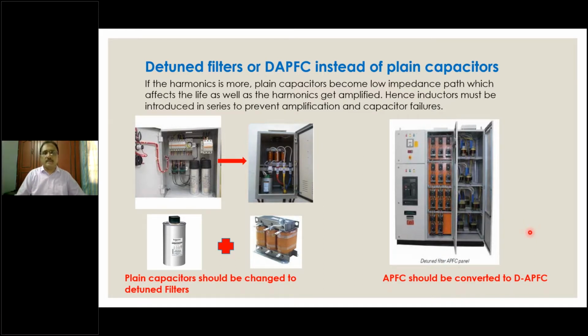So, these are some of the solutions for a fixed bank capacitor. Typically, you should use a reactor in series. This is how it will look. So a plain capacitor, cylindrical in shape, should be treated like this. In series, you have an inductor. The supply cable will come from here, go to the reactor, and from the reactor it will go to the capacitor, so that the capacitor and reactor are in series. So any fixed bank capacitor should be converted like this.